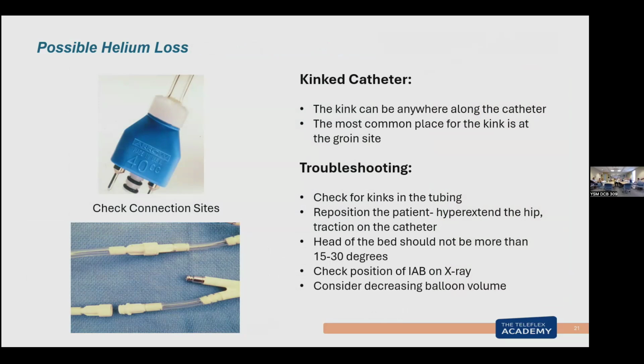Now, if you receive a patient from another institution who has a Maquet balloon in, they have that male connector on it. You're going to have to use adapters to plug into my pump. I often find the adapter is where the leak is, because it's a leak point. The male connector goes in the back of that, and there's a leak point. So my trick on that one, I did transport, so we go anywhere to pick up balloons: when you put the male connector into the adapter, you push it in and you twist. That will tighten. If it continues to leak, I have to change out the adapter. So these are two other places that can be leaks.